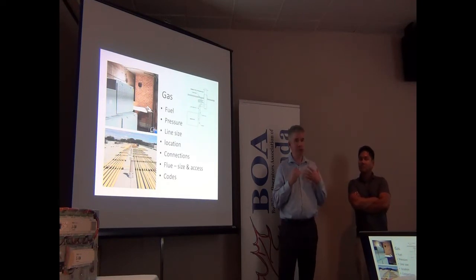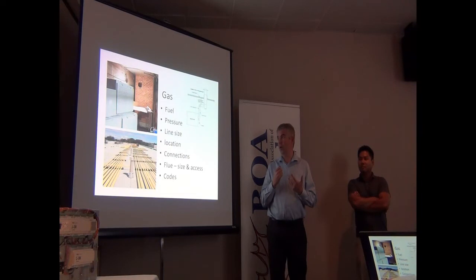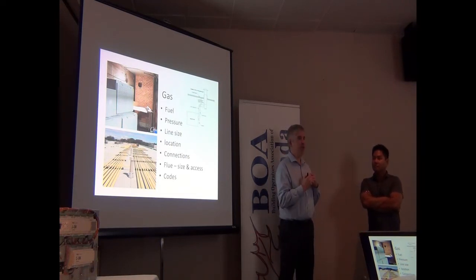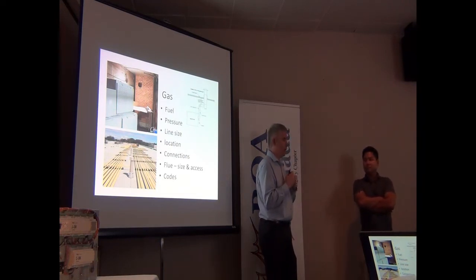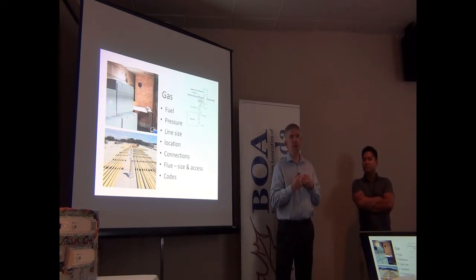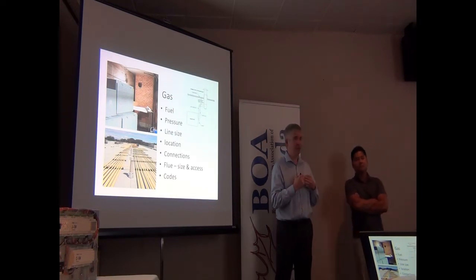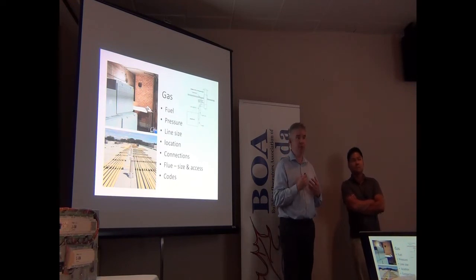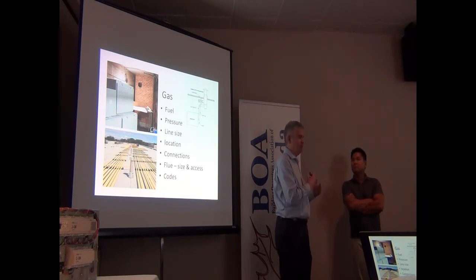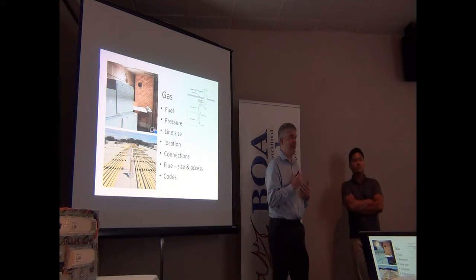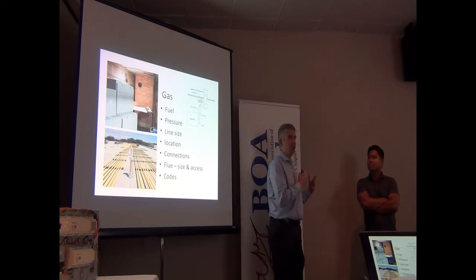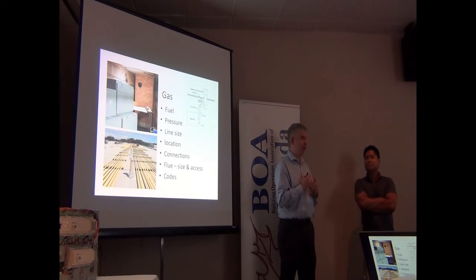Now if we're talking about changes, there could be other things to go along with it. If we're talking about adding heat load to a building, well now we're talking adding gas load to a building. Do you have the base pressure that you need in that space for those gas lines? Do you actually have the gas at the meter in the first place? Lots of buildings are tapped out in terms of gas capacity. Adding 1 million BTU could be a giant thing that might not be feasible with your meter set up, and you have to talk to the gas provider to work through that before dealing with the piping in the rest of the building.